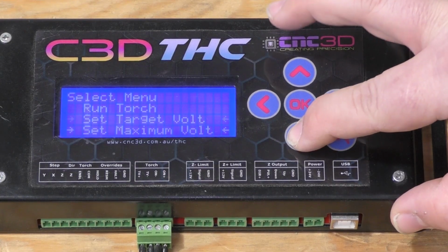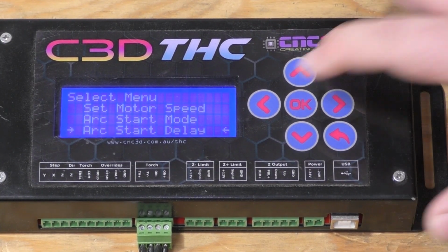and then we'll scroll down to the next menu, which is arc start delay. Arc start delay is currently set at 3000 milliseconds, which is 3 seconds. This is the time that the controller will pause. If it has not received an arc OK signal within this time, it will send an abort or an e-stop signal to the controller. If it does receive an arc OK signal within this time period, it will resume the job.